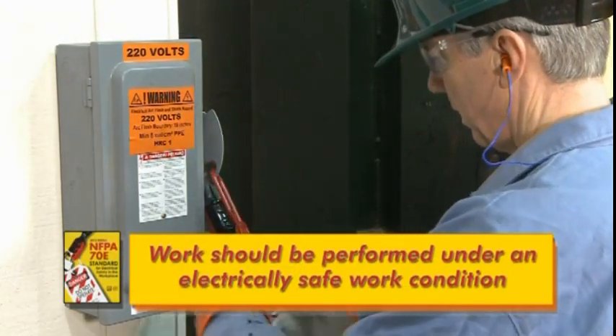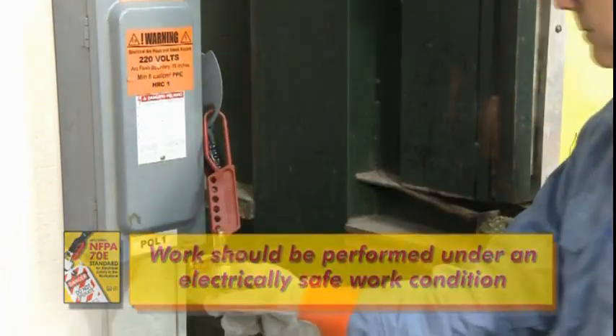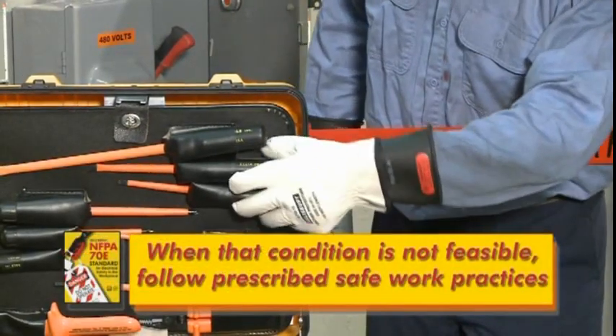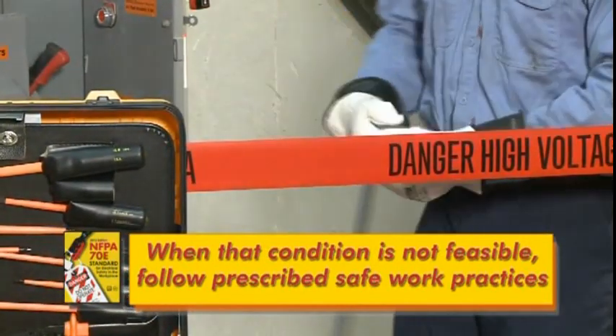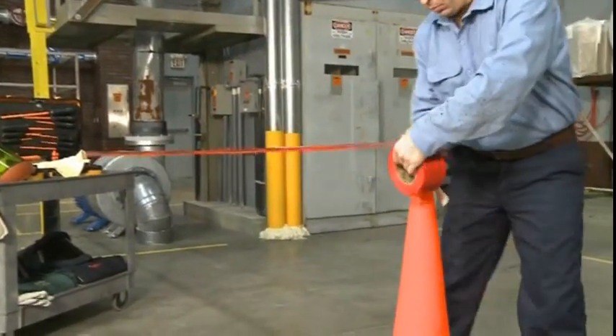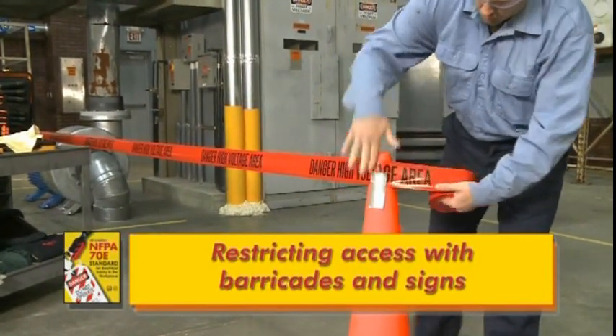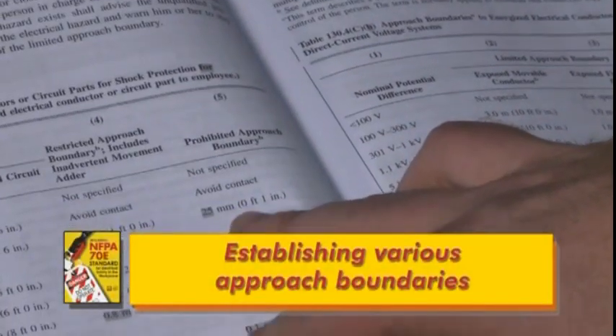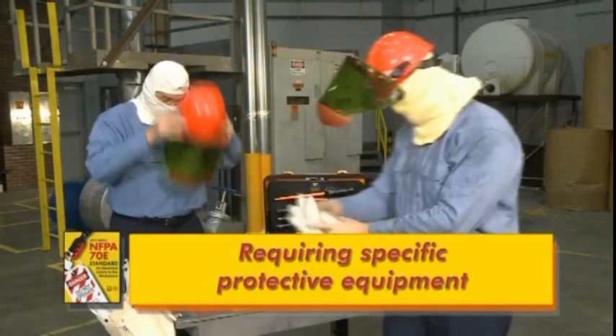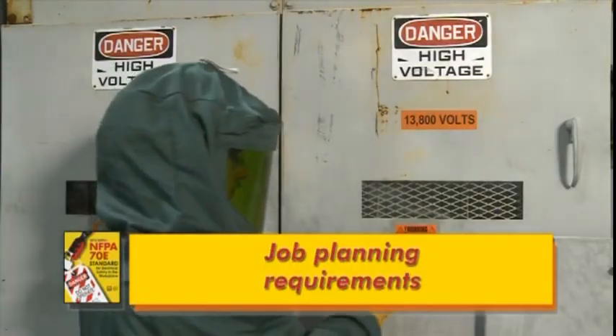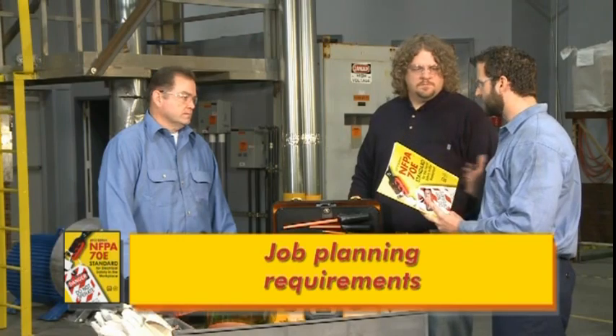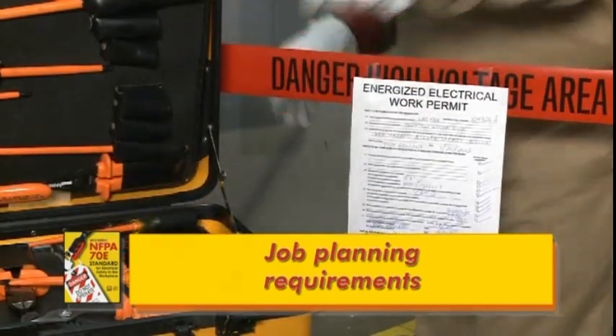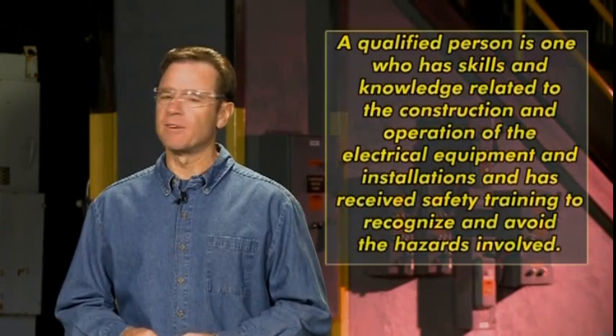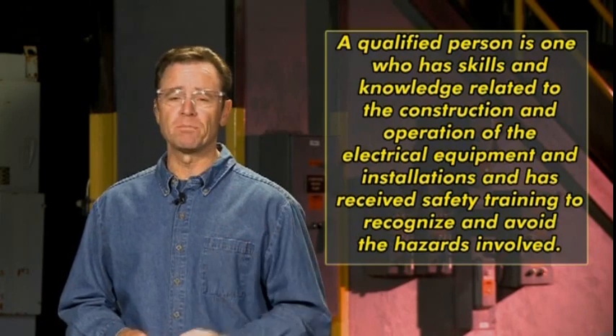Other safe work requirements include that work be performed under an electrically safe work condition whenever it is feasible to do so. And when creating an electrically safe work condition is not feasible, following prescribed safe work practices. These work practices may include restricting access with barricades and signs, establishing various approach boundaries, requiring specific protective equipment for electric shock and arc flash hazards, and job planning requirements which include hazard analysis, job safety briefings, and the use of energized work permits. Let's briefly revisit the definition of a qualified electrical worker and examine this very important point.